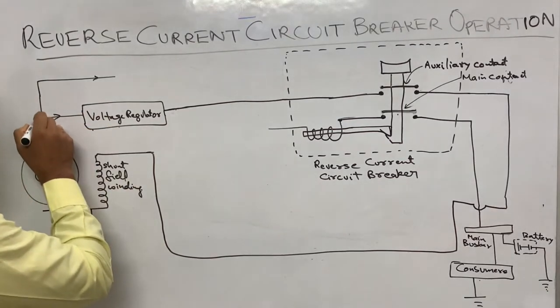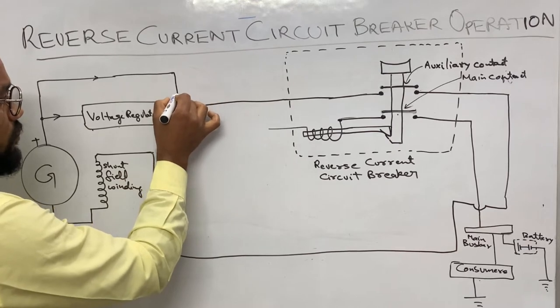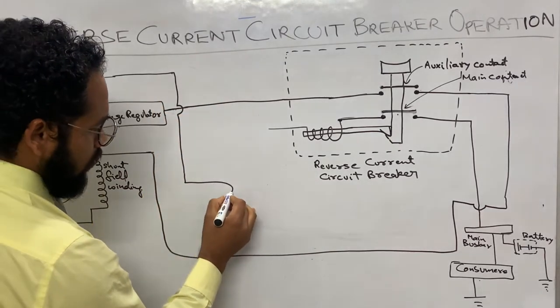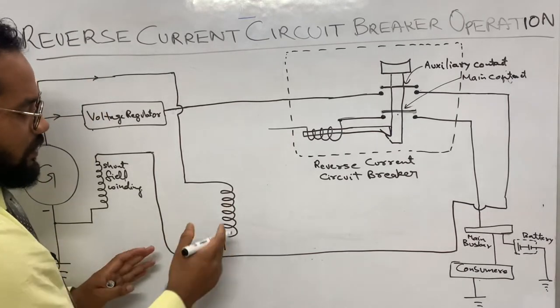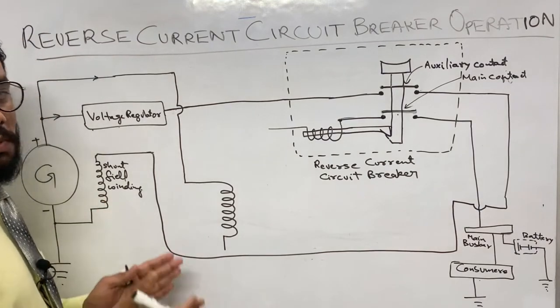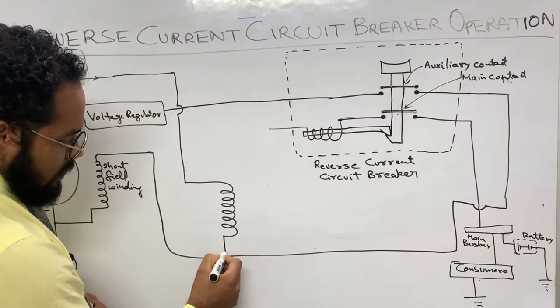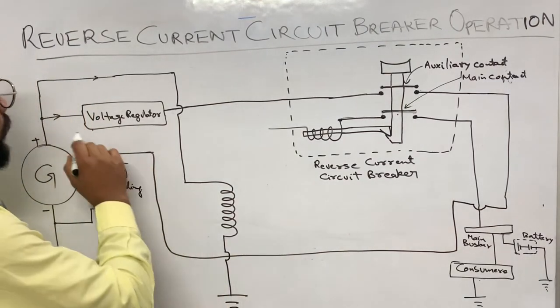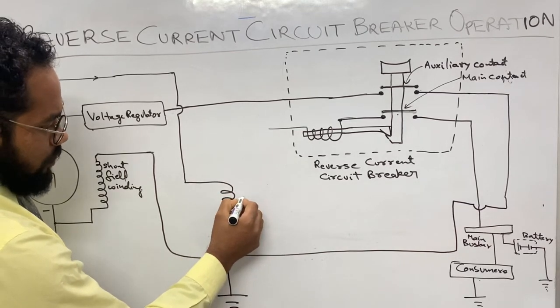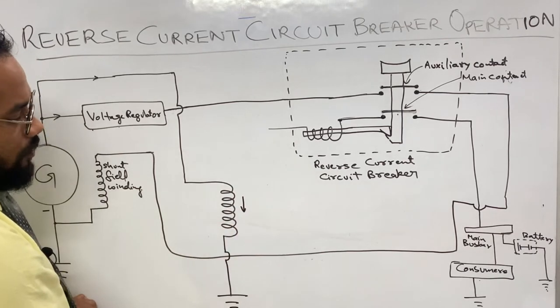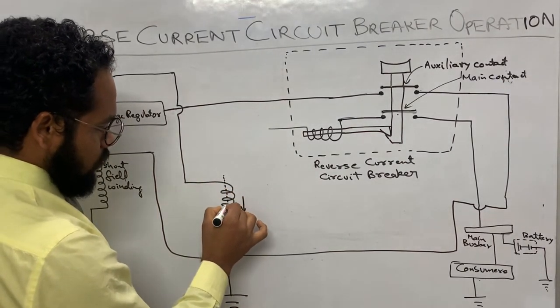The output is also taken and given to the reverse current cutout relay. This is the voltage coil of the reverse current cutout relay. In the reverse current cutout there are two coils: one is the voltage coil and the other is the current coil. The voltage coil has many turns of thin copper wire and gets a grounding path. When the output is given to this voltage coil, the coil gets energized and produces a magnetic effect, causing a contact to close.